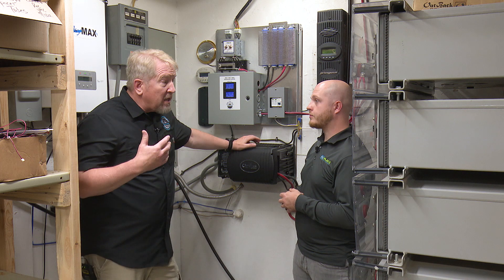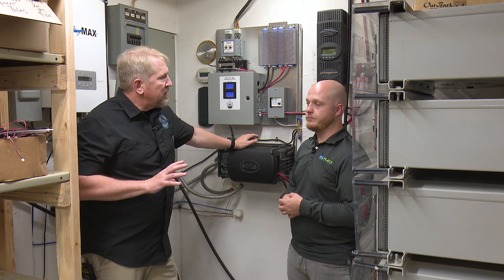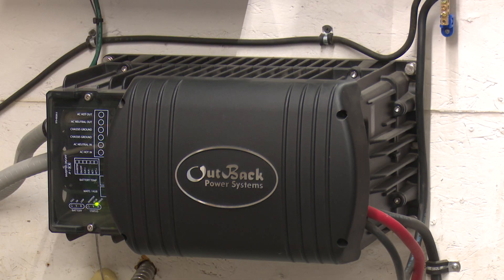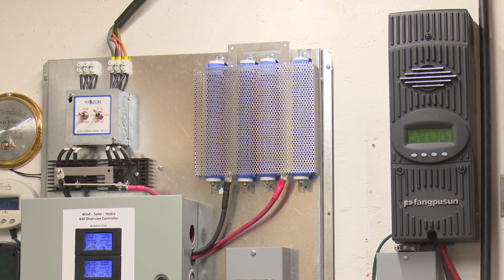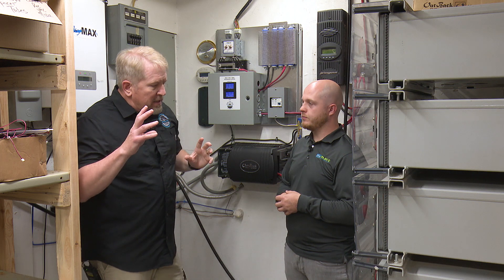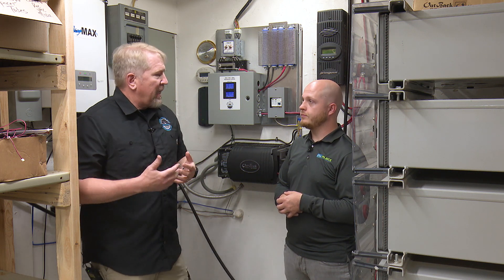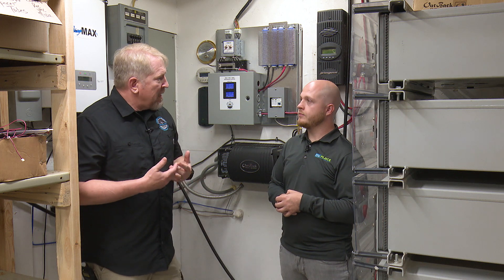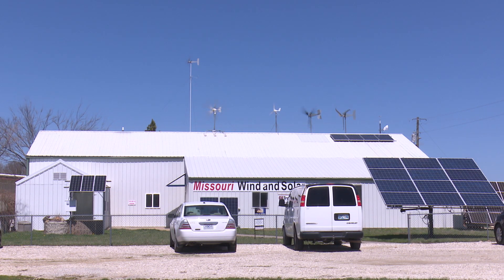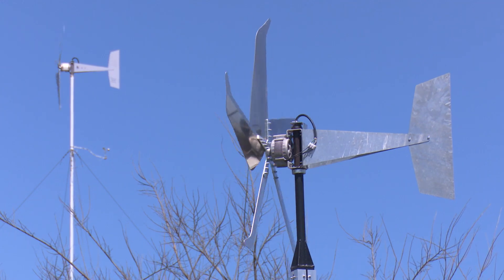This is one of the brands that we carry — there are several different ones. Our sales engineer would talk with you and decide what's best for your environment. Basically what this unit does is it's monitoring the grid, monitoring the power coming in, and monitoring what power we have in the batteries. We've got wind and solar coming in, so the system is balancing all of that and deciding where to take power from. If you lose power, the system says grid's gone and pulls from the batteries — you'll have very limited, if any, notice that there's been a drop off.